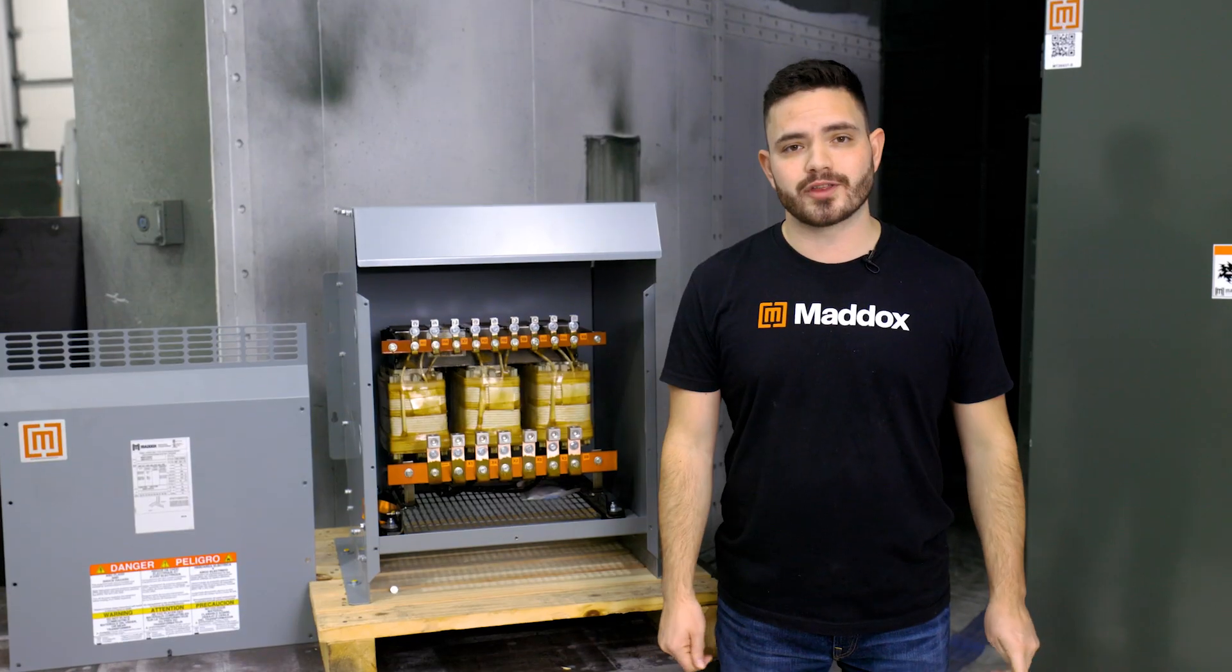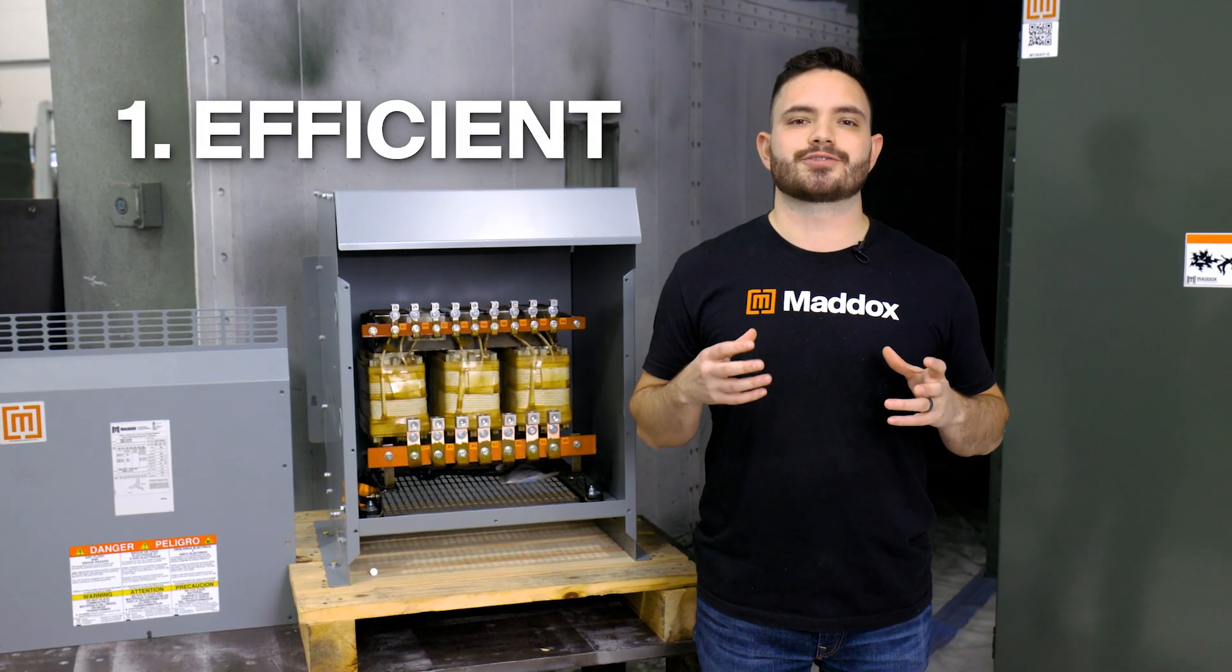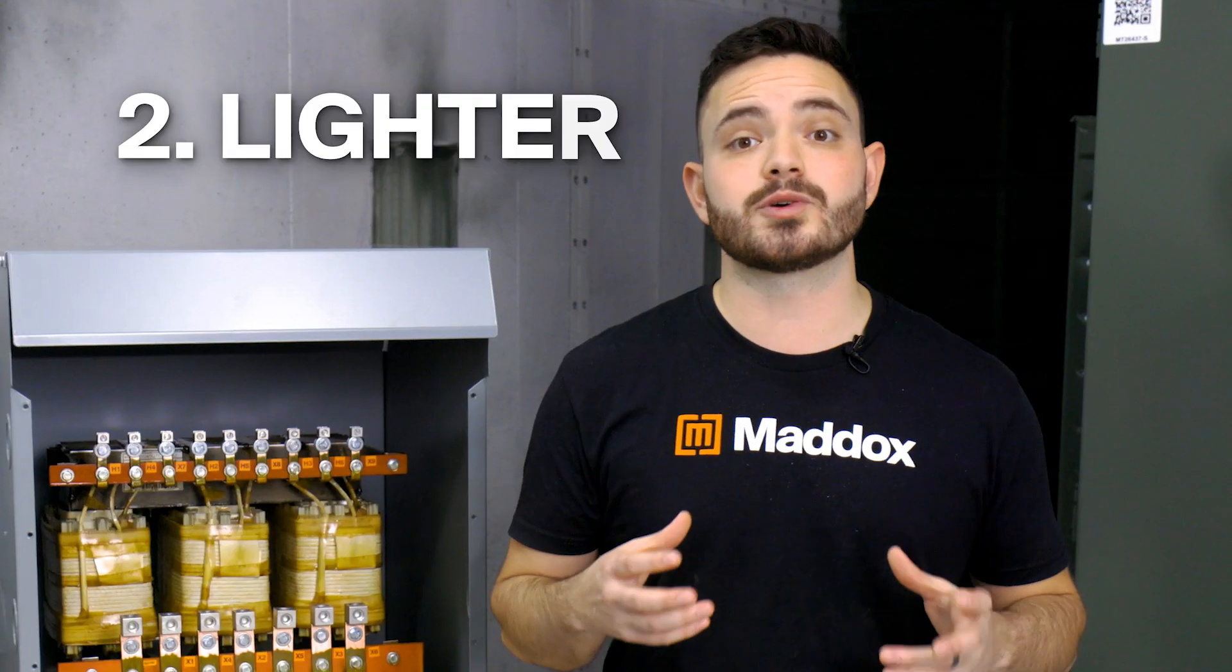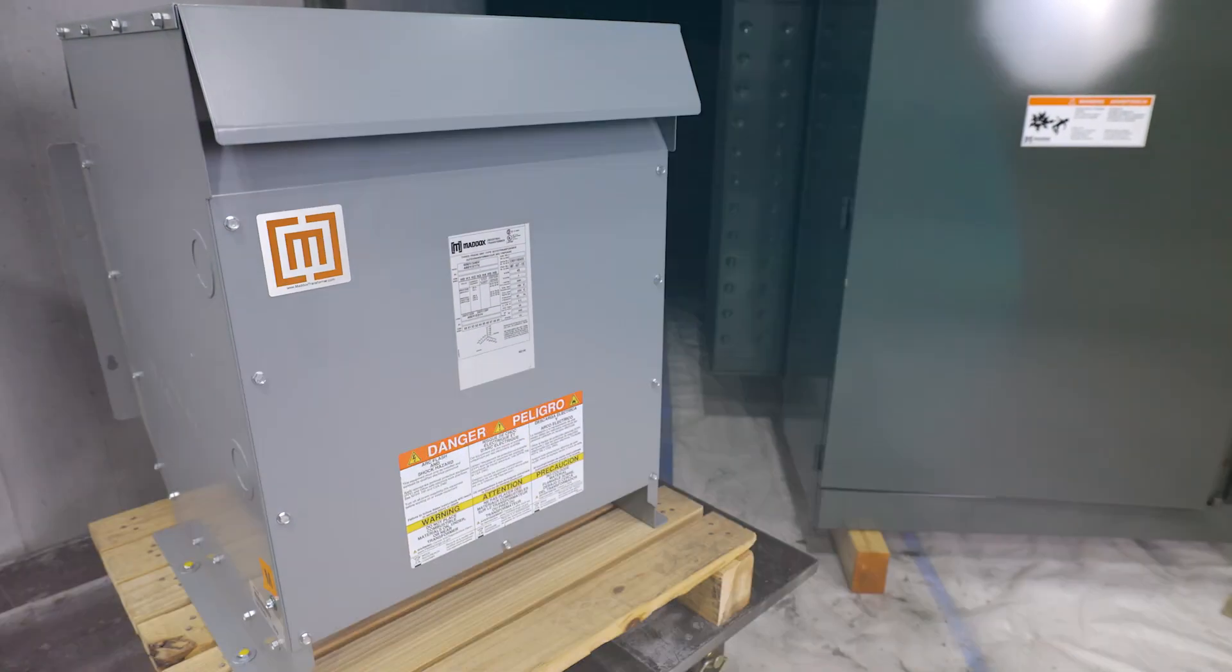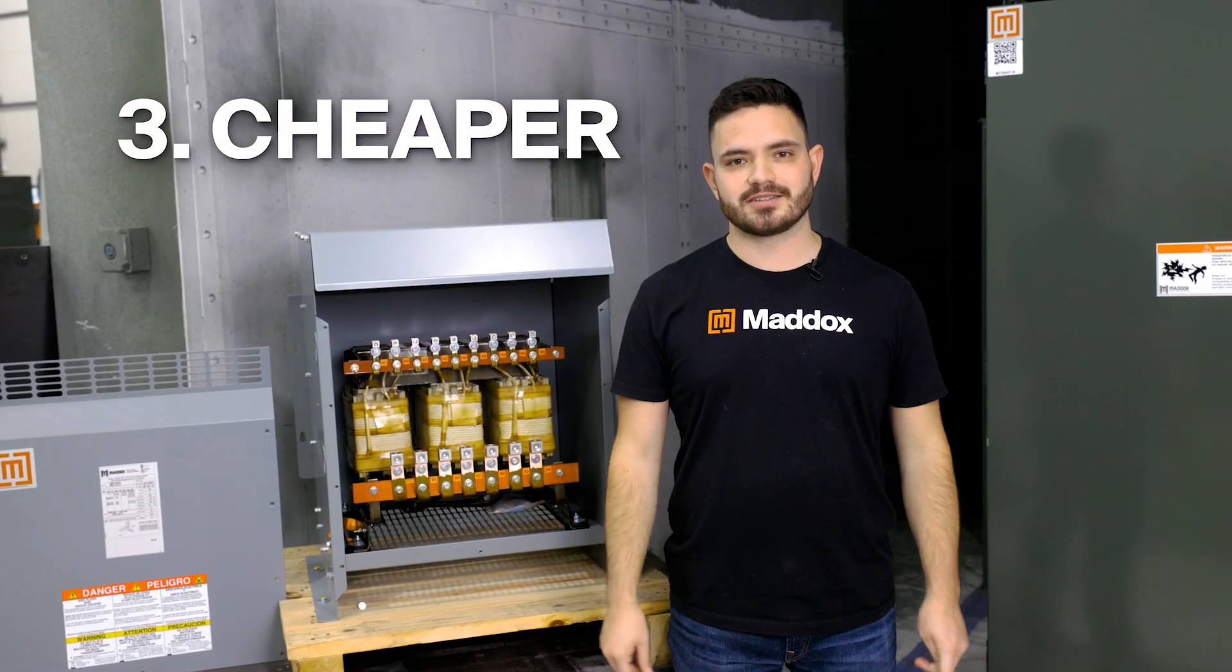Now auto transformers have a few massive advantages over their isolating counterparts. Because of the direct connection between the primary and secondary, auto transformers are extremely efficient. They're also lighter and more compact. And because they use less material, they're much cheaper than traditional isolation transformers.